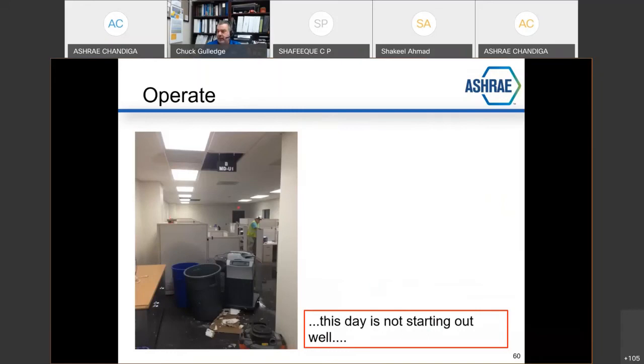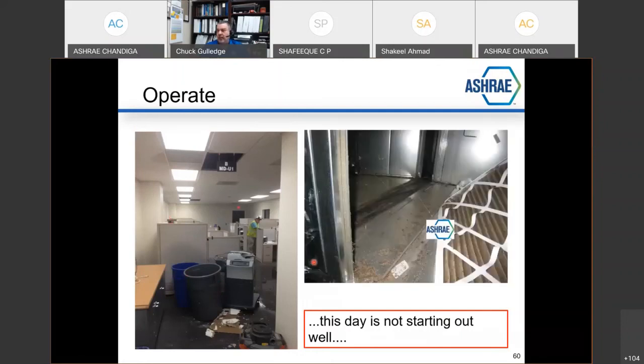This day is not starting out well. You can imagine with all the water you see on the floor and all the cans that are collecting the drips and the fact that a ceiling tile is missing now and an expensive copier is underneath that, this is not a good day for somebody. And I got called to the carpet to explain myself with what were you doing? Why does your system not work very well? And it all came back to an air handler sitting above this space where the filter had gotten so dirty, it had actually collapsed. And this was the position it was found in.